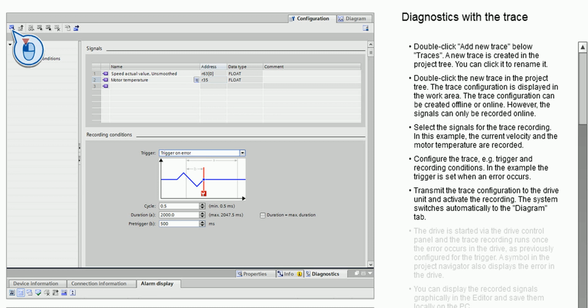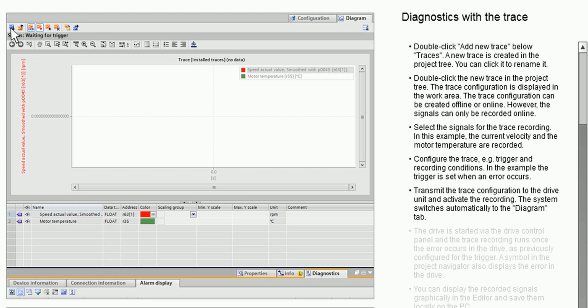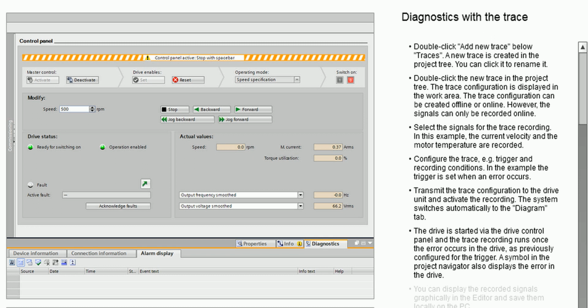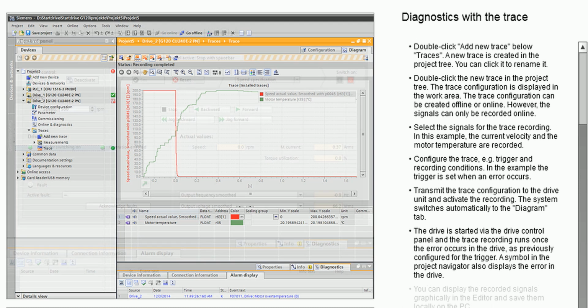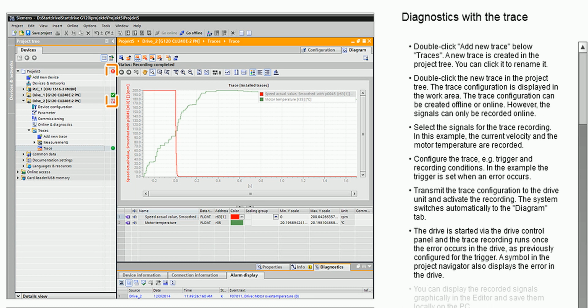Transmit the trace configuration to the drive unit and activate the recording. The system switches automatically to the Diagram tab. The drive is started via the drive control panel, and the trace recording runs once the error occurs in the drive, as previously configured for the trigger. A symbol in the Project Navigator also displays the error in the drive. You can display the recorded signals graphically in the editor and save them locally on the PC.